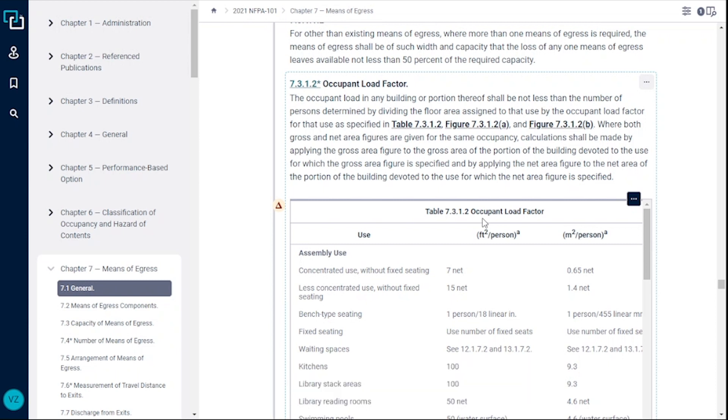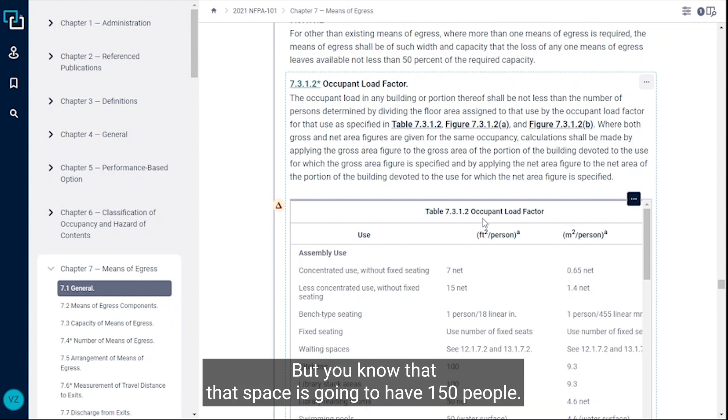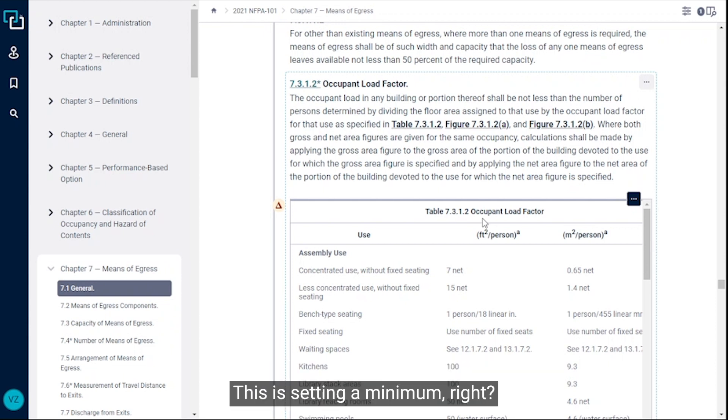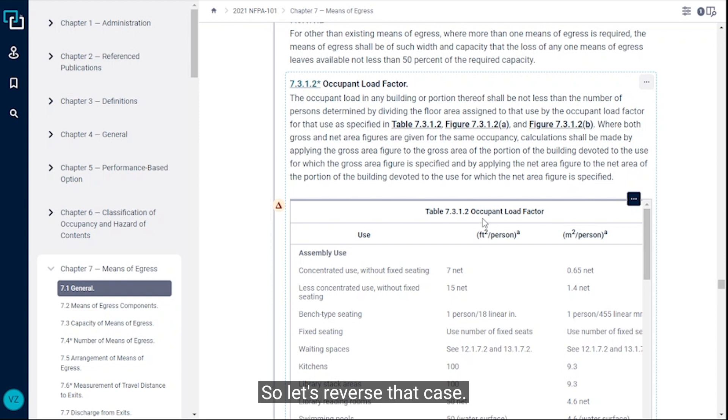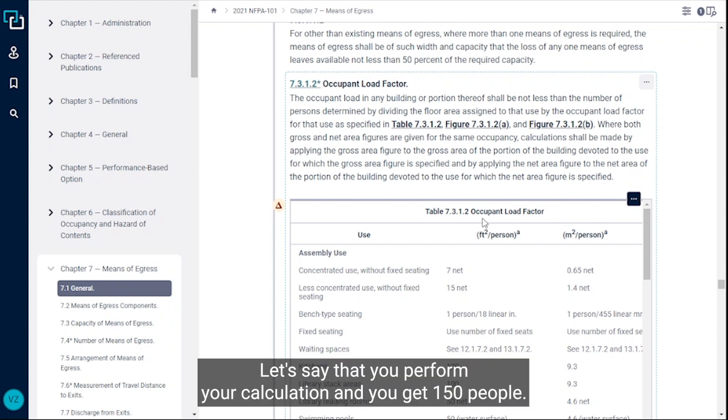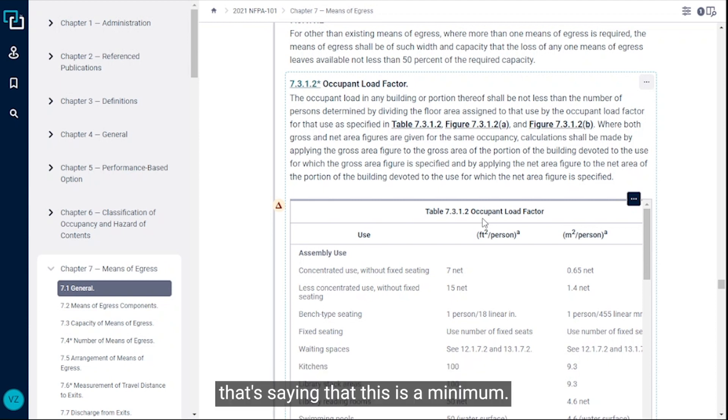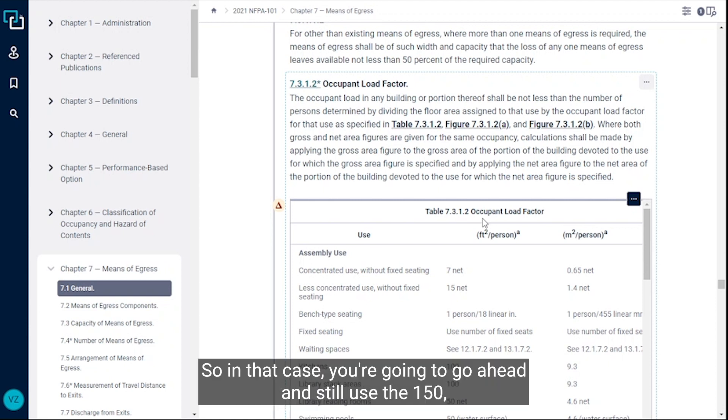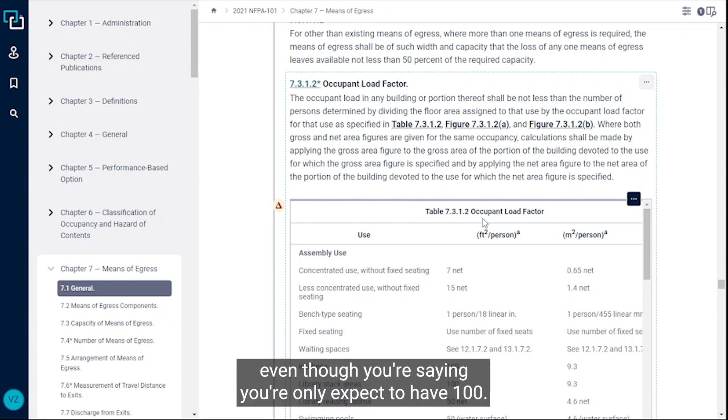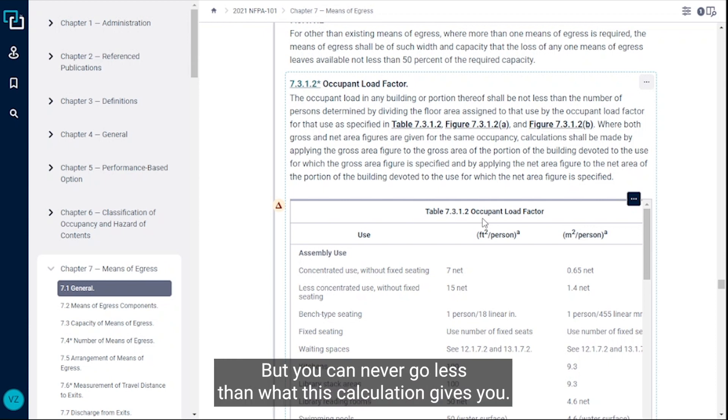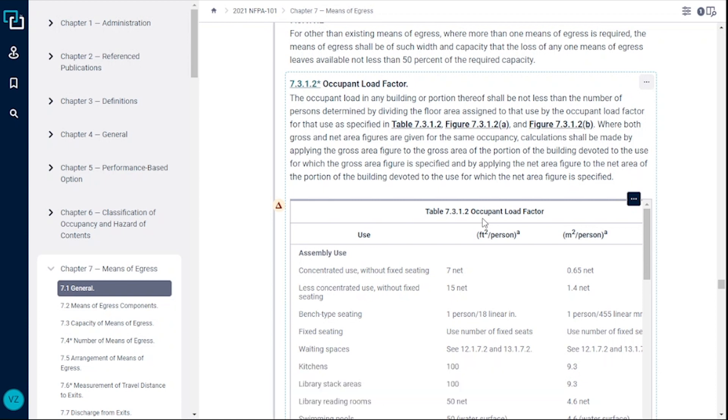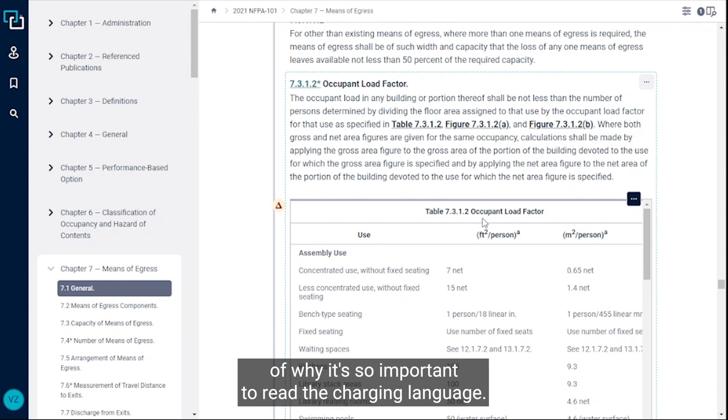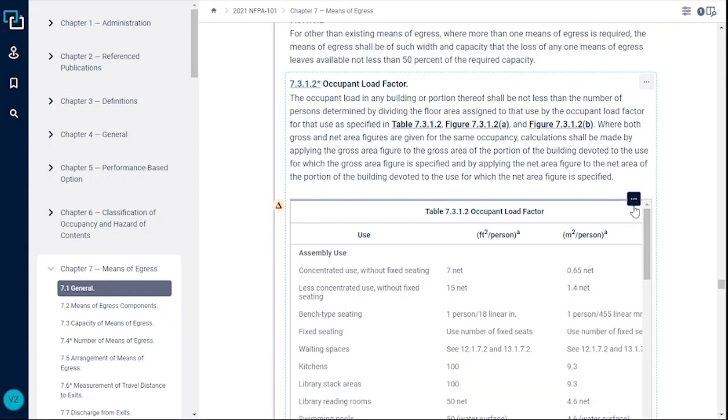Let's reverse that case. Let's say that you perform your calculation and you get 150 people, but you're saying I know I'm only going to have 100 people in this space. That's saying that this is a minimum, so in that case you're going to go ahead and still use the 150 even though you're saying you only expect to have a hundred. You can never go less than what this calculation gives you. That's the first reason, or just one example of why it's so important to read the charging language.